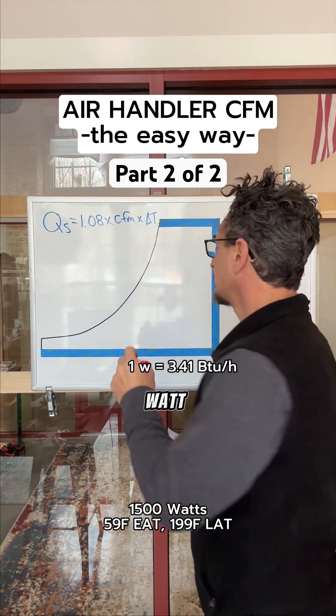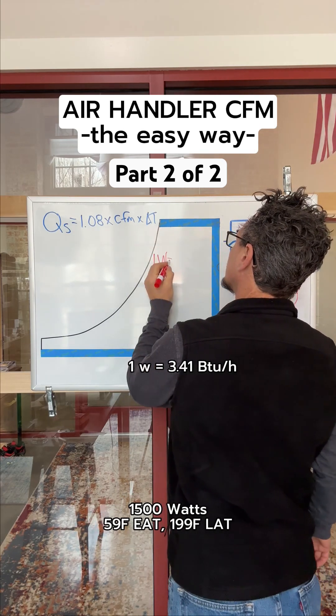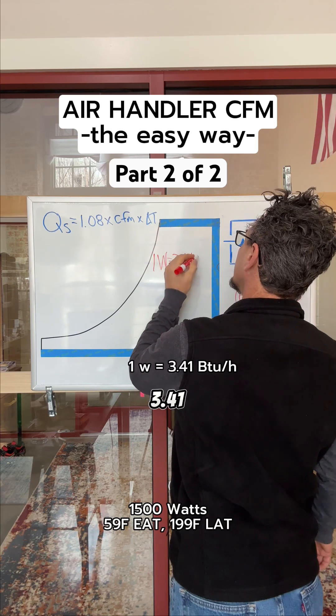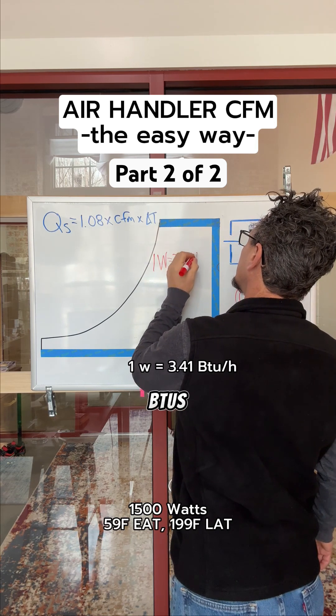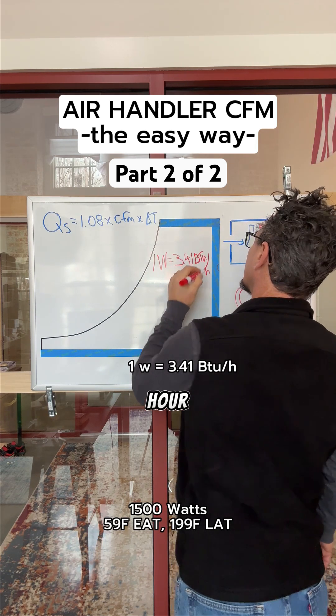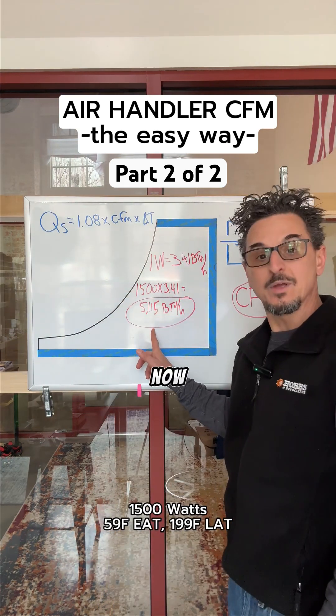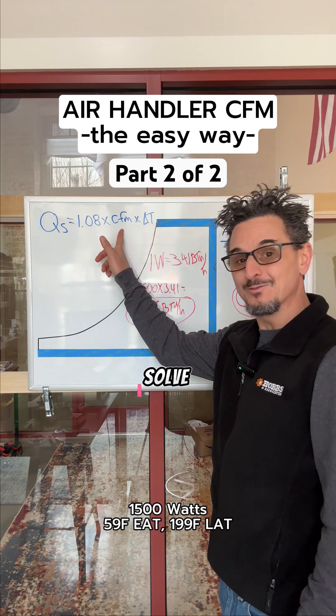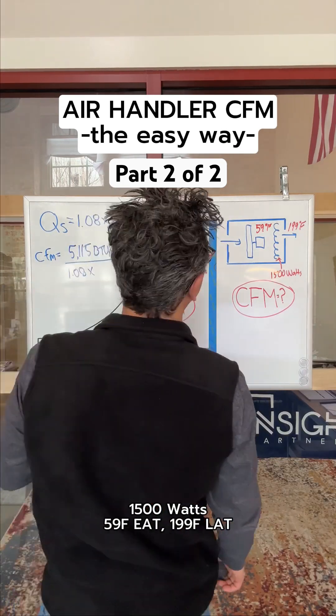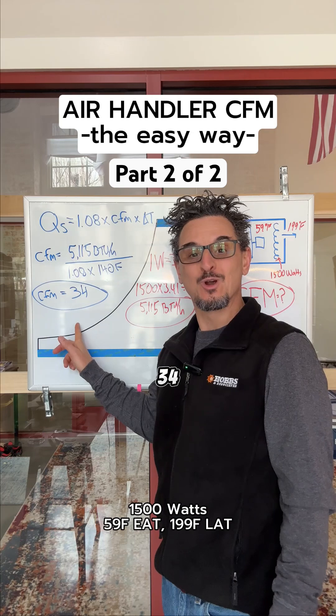One watt equals 3.41 BTUs per hour. So now we have the BTUs per hour, and we can solve for CFM — which equals a whopping 34 CFM.